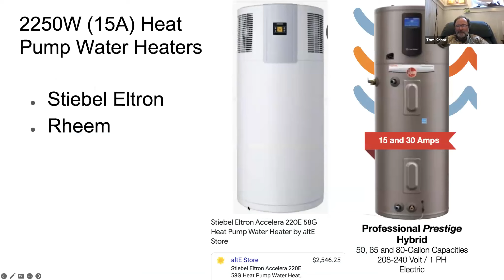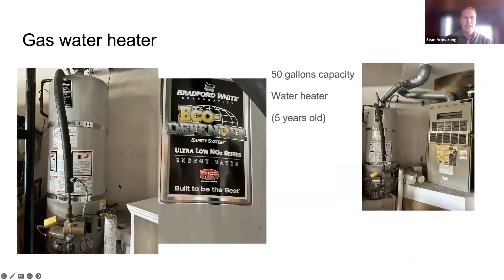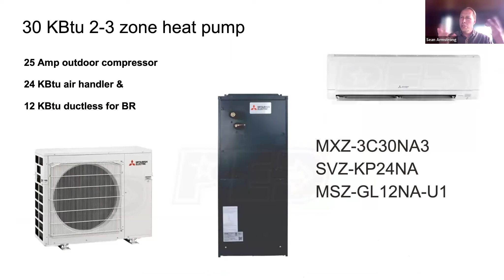And that was here. Note that this math that he's doing is showing us that at the peakiest of the peak, at the worst moment of the year, 28,000 BTUs is needed. And that's how we got to the sizing of 30 kBTUs, 30,000 BTUs per hour. Those two things match. You size your pump for the worst possible moments. And that's what Tom succeeded in doing there.